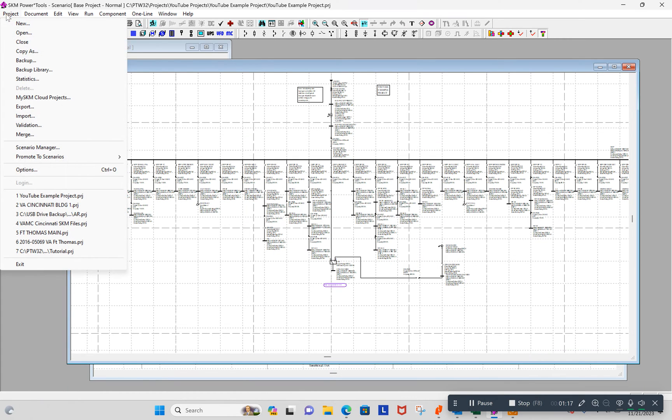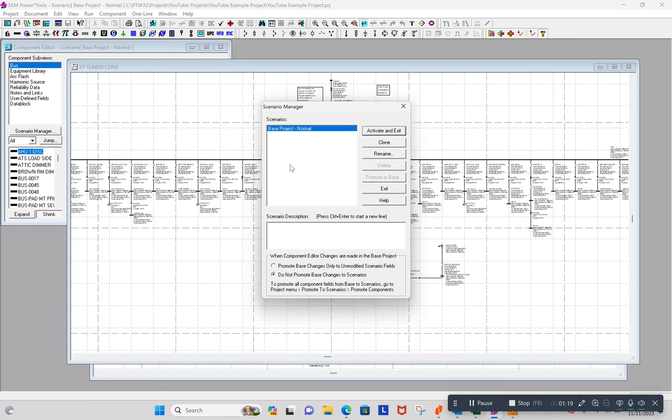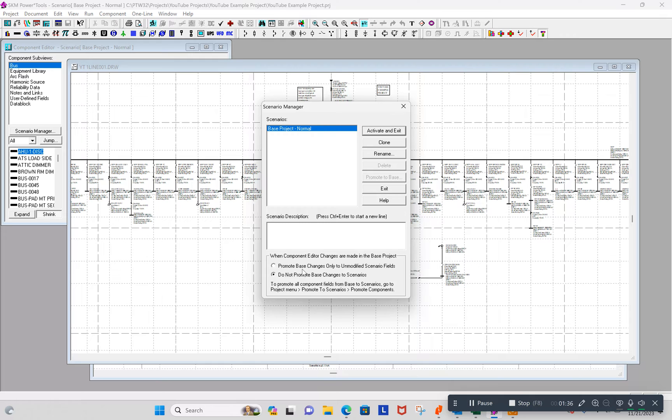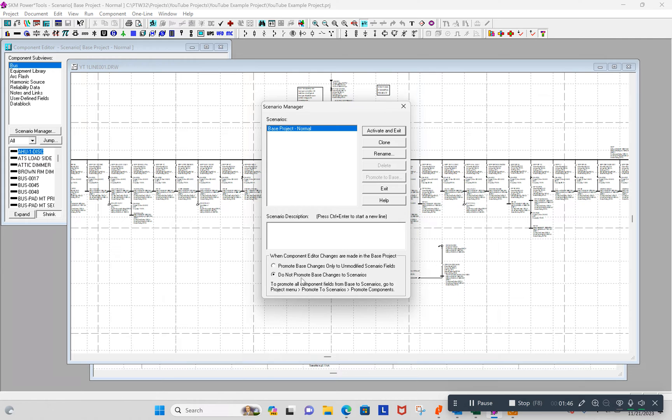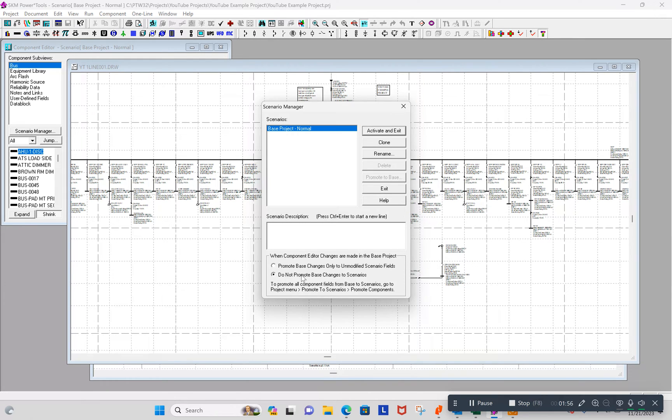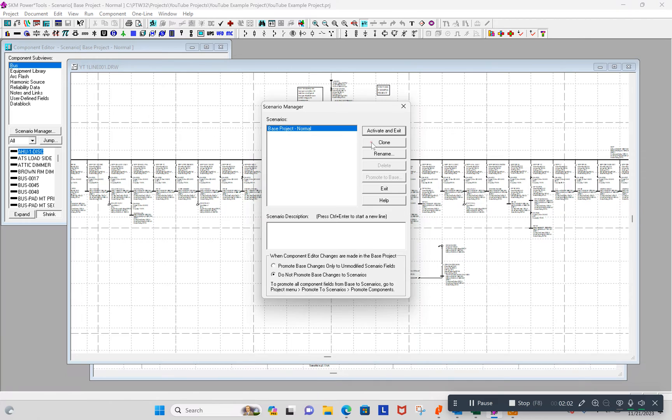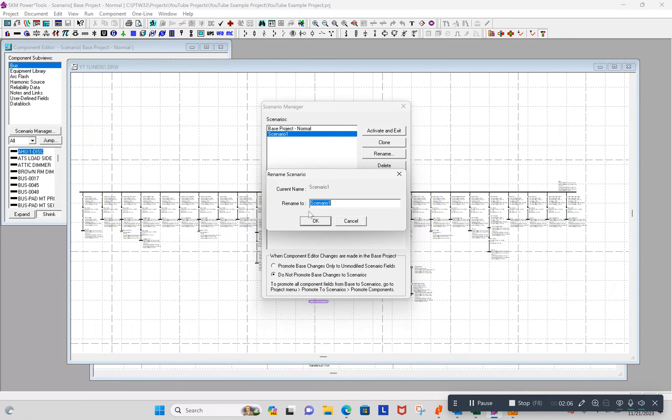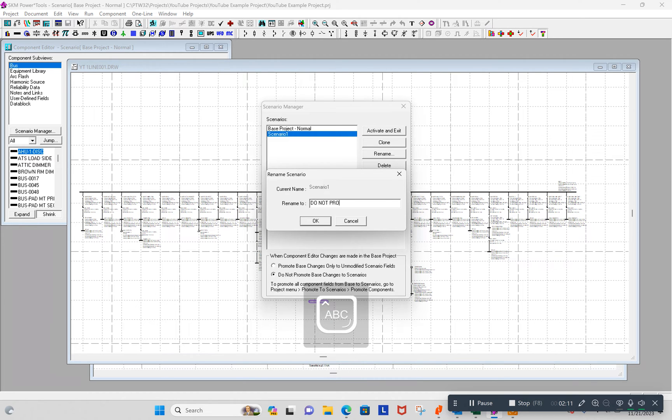So let's see what we can do with the Scenario Manager. That is up here under Project Scenario Manager. I'm going to create a scenario and I have to decide whether or not I want to promote the base changes to unmodified scenario fields or not promote the changes. What that means is do you want to automatically change your scenario anytime you change something in the base if it hadn't been modified in the scenario, or do you never want to change it? So let's just make it another scenario here. I'll demonstrate do not promote base changes. So I'm going to clone the base project and I'm going to rename this to do not promote changes.